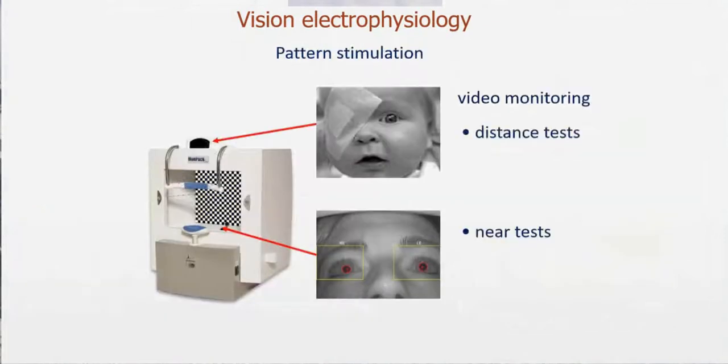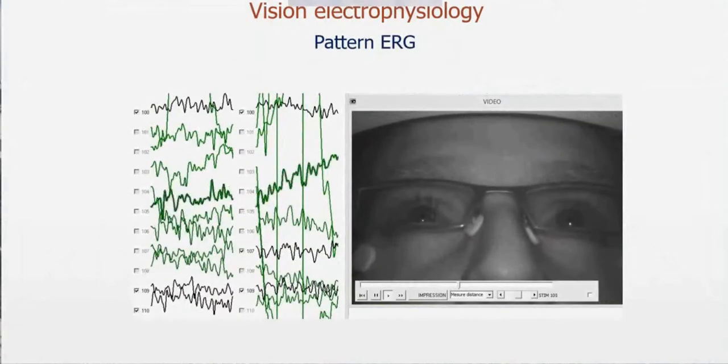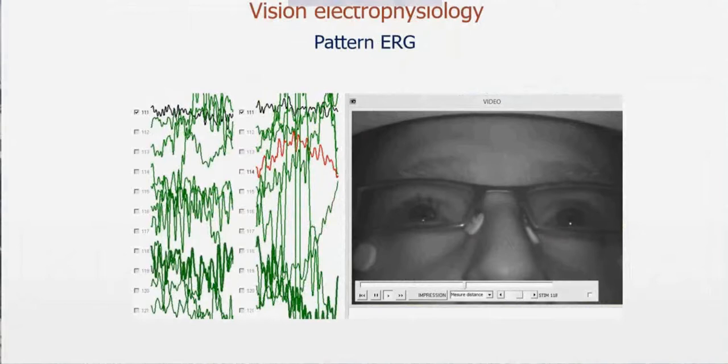One of the important features needed for electrophysiology is to monitor what the patient is doing. We have actually two cameras, one to monitor near vision tests like multifocal ERG or flash ERG, and one camera on the top to monitor exams which are performed at a distance of one meter. This is an option, but it's very important specifically if you deal with young children because you want to know if they are looking at the monitor or if you are dealing with malingering patients.